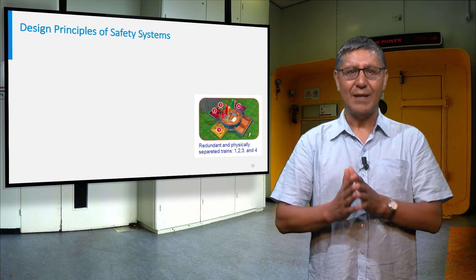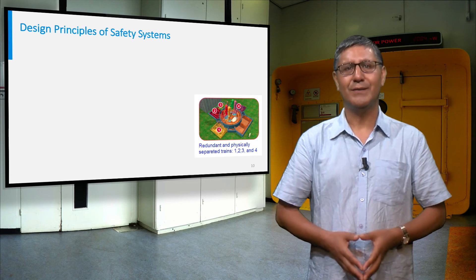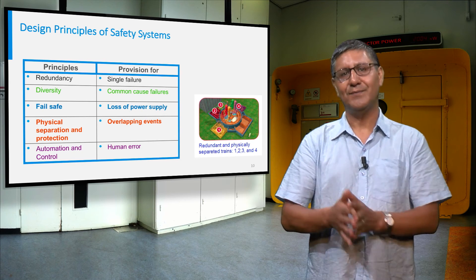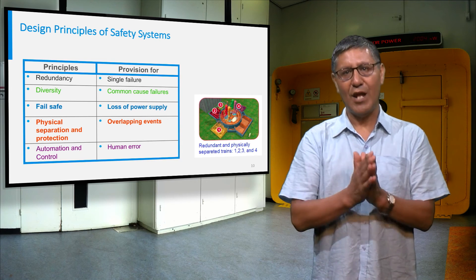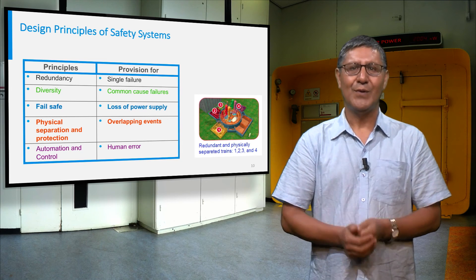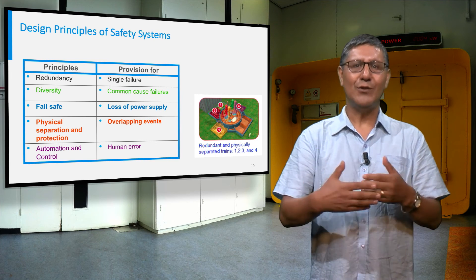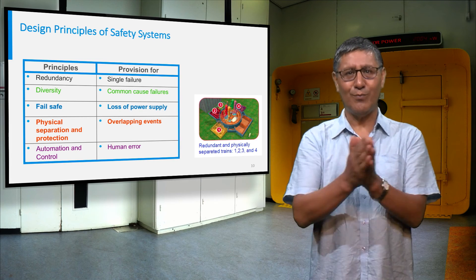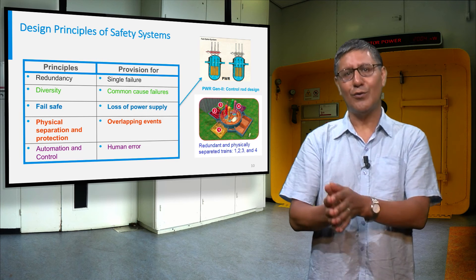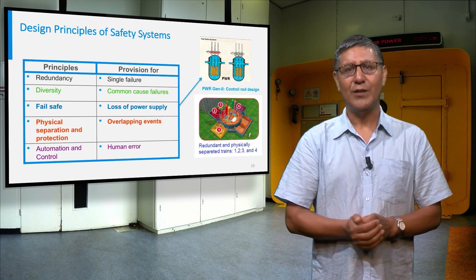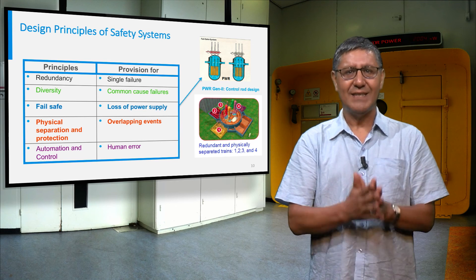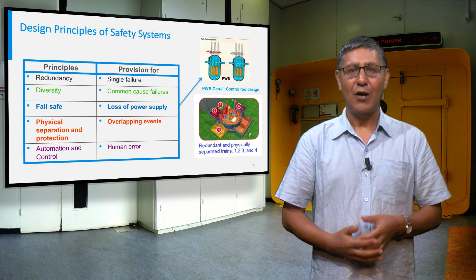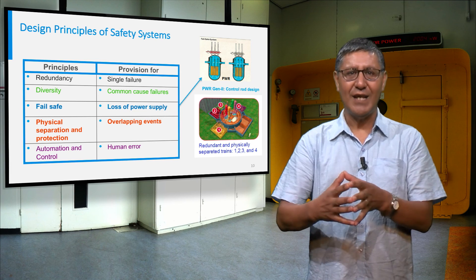Safety systems are subjected to higher design requirements. The main design principles and their purpose are listed on this slide. Redundancy is helpful in case of single failure, while diversity in design is needed to improve resilience against common cause failures. The fail-safe principle helps in case of loss of power supply, for example for the control rods of a nuclear reactor core. Physical separation is essential against overlapping events such as flooding. Finally, automation in the nuclear power plant reduces the amount of human errors.